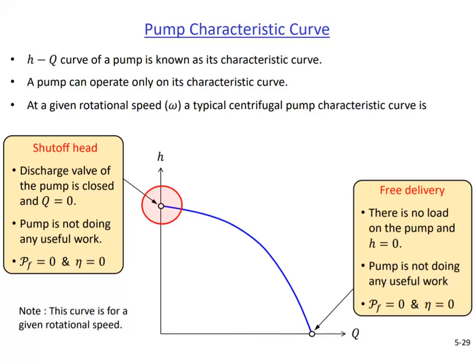Shutoff corresponds to the maximum possible head that can be delivered by the pump, but this happens at zero flow rate. This condition is obtained when a valve on the discharge side of the pump is closed. The pump cannot create any net flow rate. With zero flow rate, power delivered to the fluid is zero, and the efficiency is also zero. Operating a pump at this condition for an extended period of time can damage it.